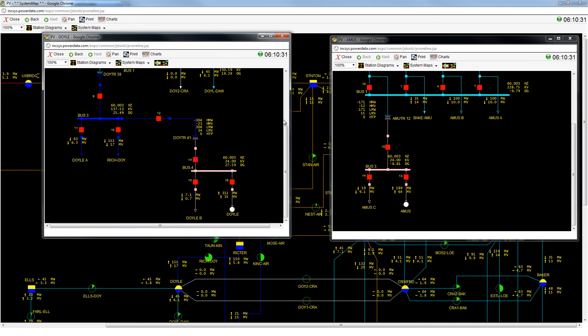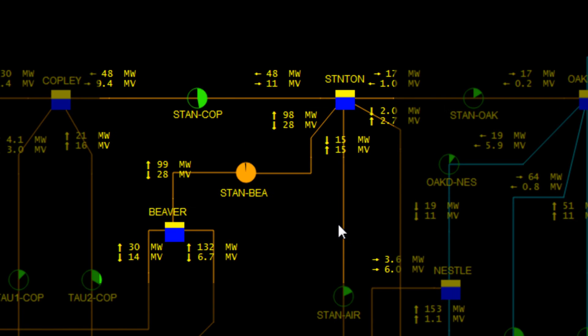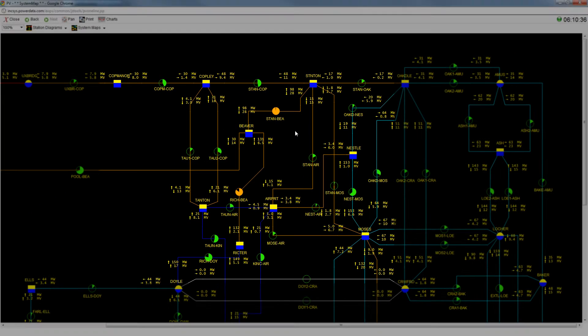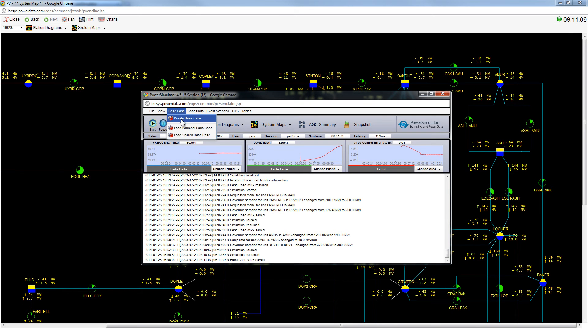With both generators nearly at their set point, we can see that the line has significantly unloaded. Let's reload the base case so that we can walk through the process step by step.